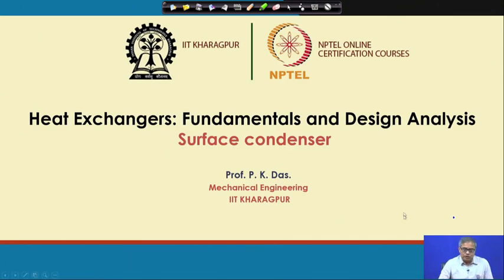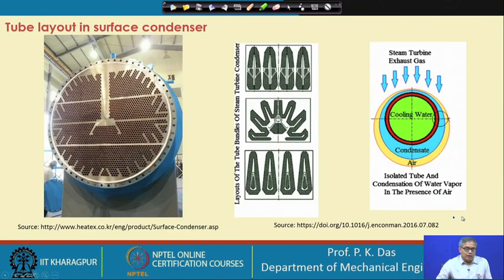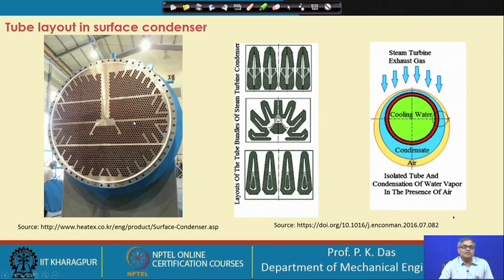This is the current lecture on surface condensers. I am showing a typical surface condenser of a steam power plant. Looking carefully at this diagram, you can see the tube layout. First, the tubes are laid in a very dense configuration, and the arrangement is not in-line but staggered — this is very important. In a steam power plant surface condenser, there are different tube layout patterns, some of which are shown here from published literature.